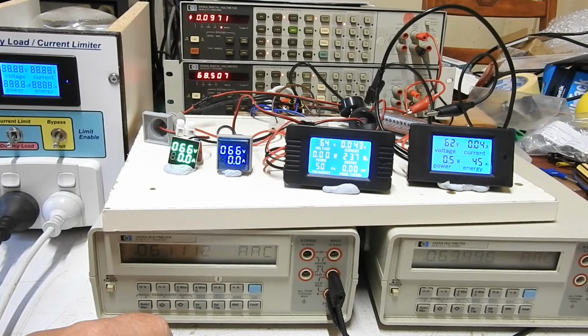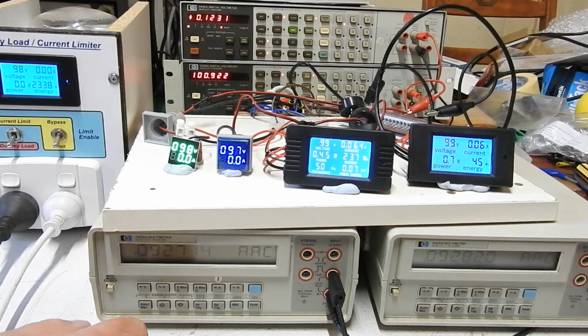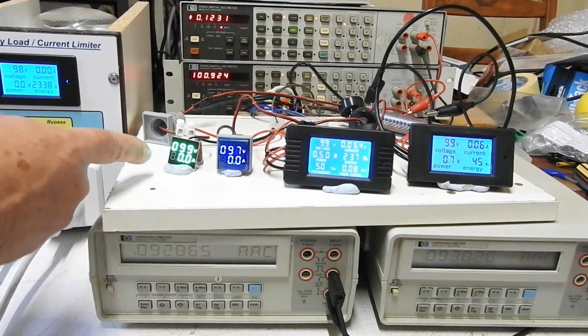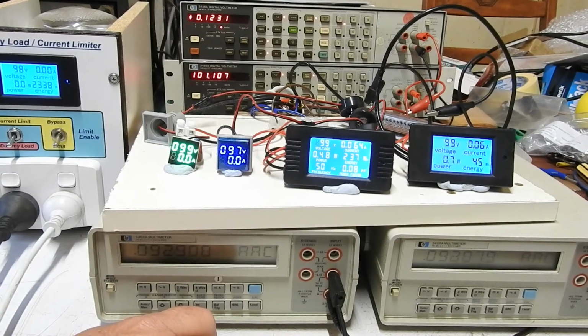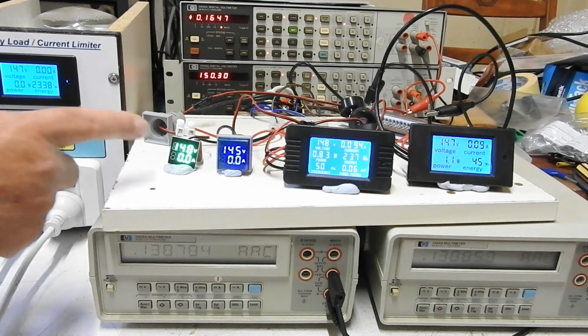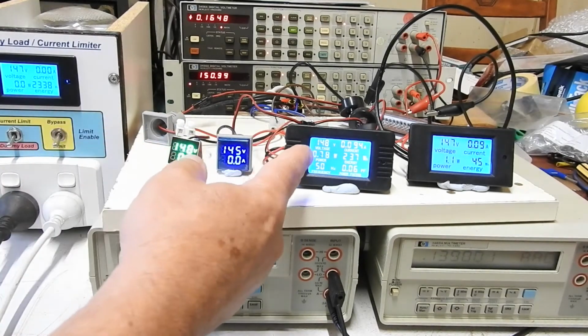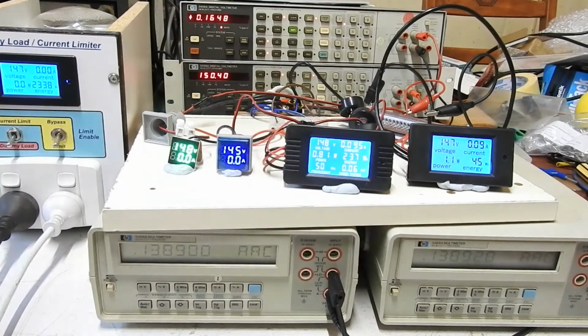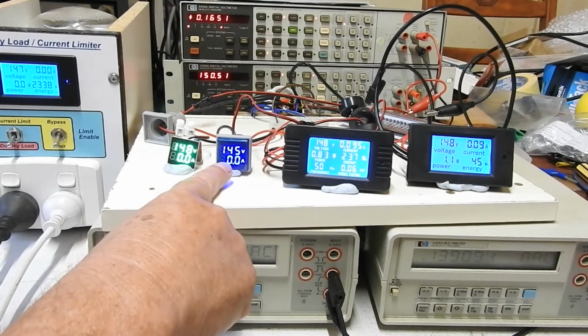Starting to work at 70 volts, 80 volts and they're working. Let's take it to 100 as measured by the meter at the back, the HP at the bottom, and see how they agree. This one's saying 98, 99, 97, 99, 99 - all pretty close on voltage. At 150: 147 is a bit low, 148, 145, 148, 147. So they're all reading a few volts low, this one being the worst.